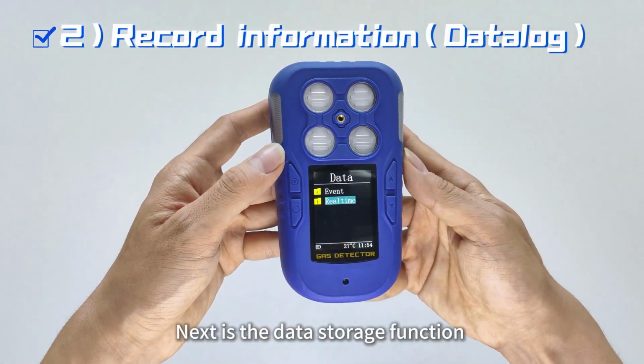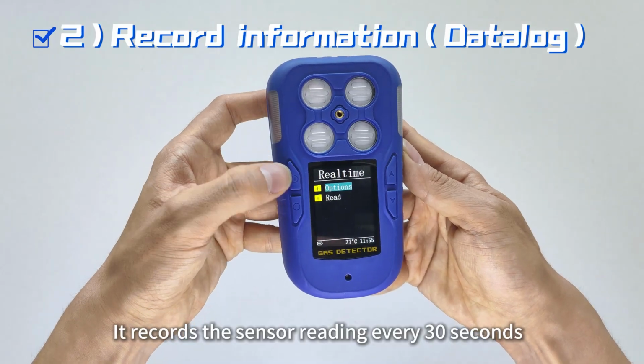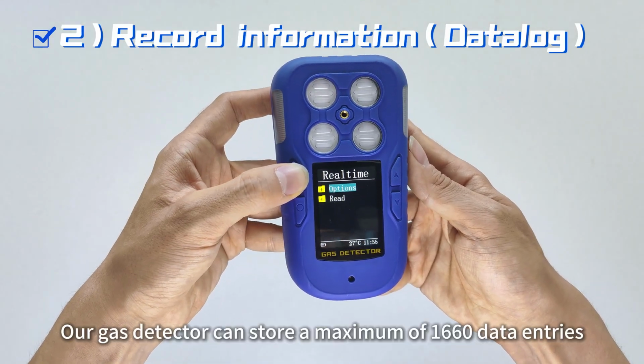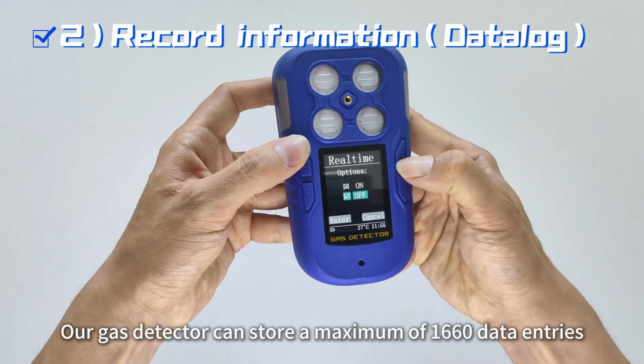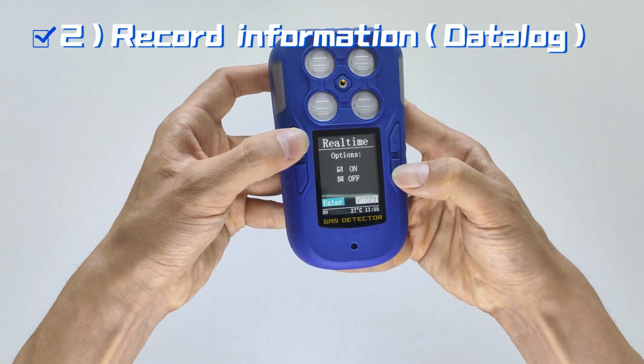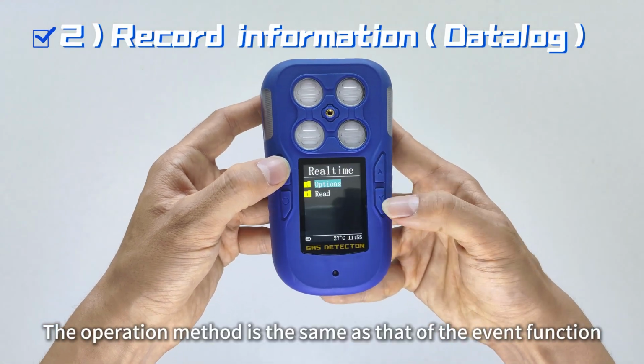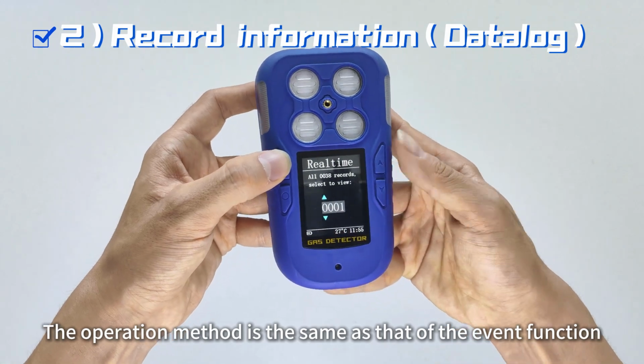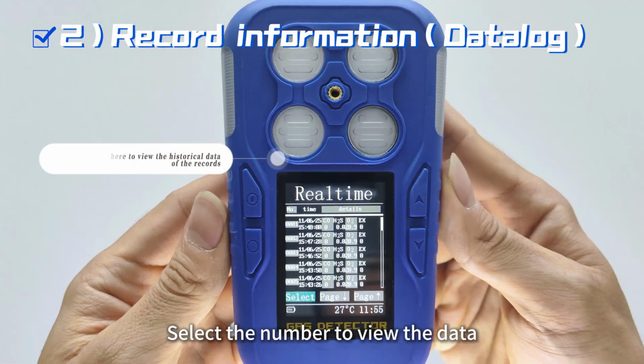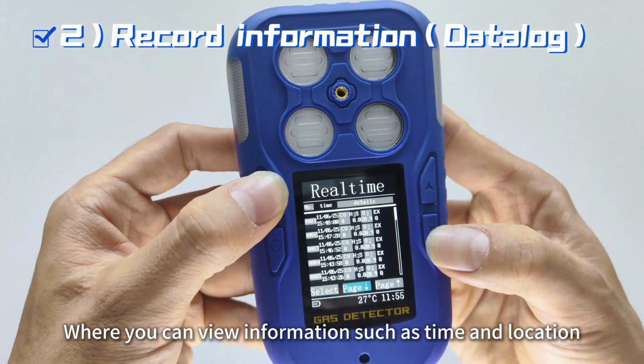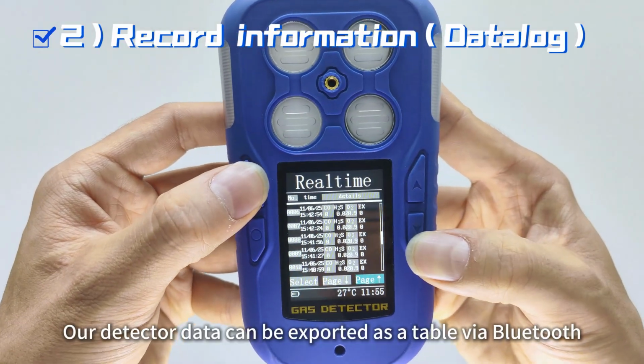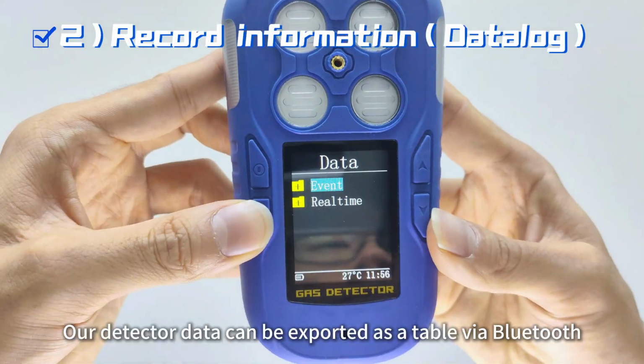Next is the data storage function. It records the sensor reading every 30 seconds. Our gas detector can store a maximum of 1660 data entries. The operation method is the same as that of the event function. Select the number to view the data, where you can view information such as time and location. Our detector data can be exported as a table via Bluetooth.